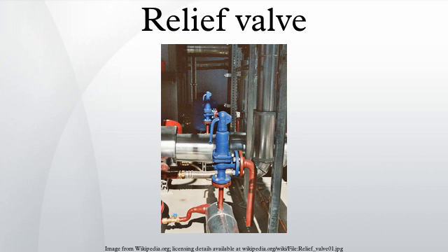Safety valve: used in gas service. Most SVs are full lift or snap acting, in that they pop completely open. Safety relief valve: a relief valve that can be used for gas or liquid service. However, the set pressure will usually only be accurate for one type of fluid at a time.